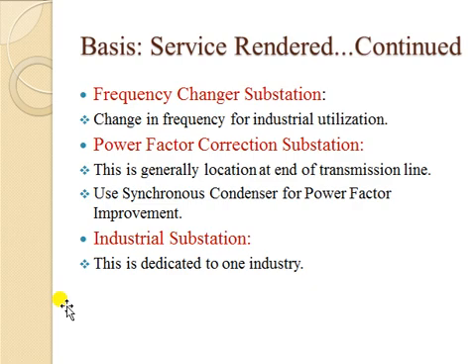There are some more applications. You can change the frequency, which may be required for industrial utilization — some industries require different types of frequencies, and that can be changed from substations. There is also power factor correction: using a synchronous condenser, which is an over-excited synchronous motor that acts like a capacitor and inputs reactive power into the system. That substation is called a power factor correction substation. There are also industrial substations dedicated to a specific industry.